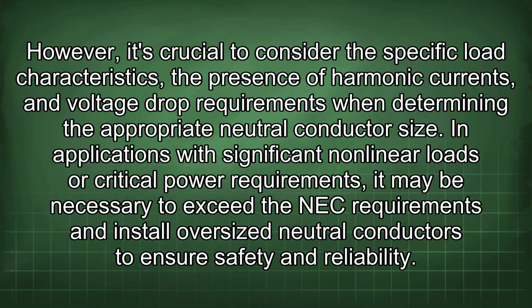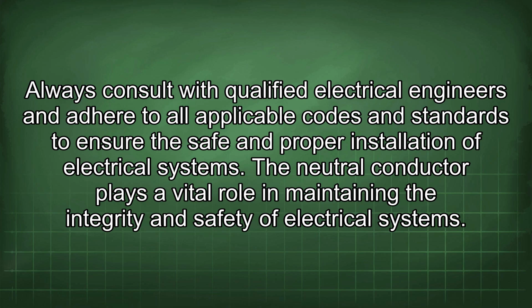However, it's crucial to consider the specific load characteristics, the presence of harmonic currents, and voltage drop requirements when determining the appropriate neutral conductor size. In applications with significant nonlinear loads or critical power requirements, it may be necessary to exceed the NEC requirements and install oversized neutral conductors to ensure safety and reliability. Always consult with qualified electrical engineers and adhere to all applicable codes and standards to ensure the safe and proper installation of electrical systems. The neutral conductor plays a vital role in maintaining the integrity and safety of electrical systems.